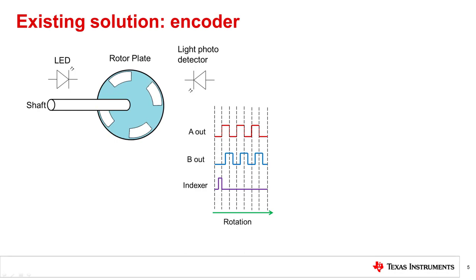These pulses correspond to the rotor movement. By monitoring both the number of pulse sequences and the relative phase of signals A and B, it is possible to track both the position and direction of rotation. The index pulse, which is generated one time for every revolution, helps the controller determine the absolute position of the encoder. Depending on the encoder resolution and the chosen step mode — either full step or microstepping — the number of encoder outputs for each input step interval will be different.